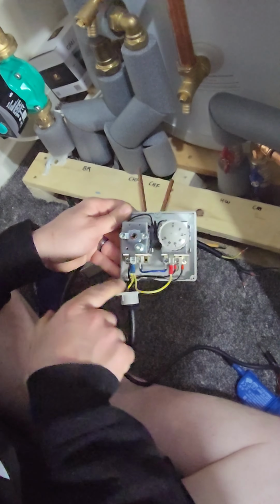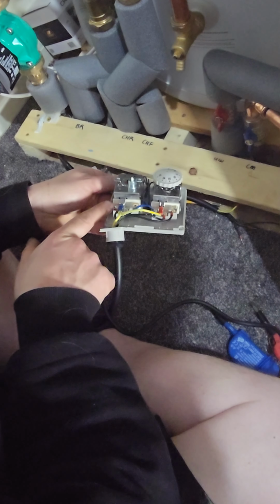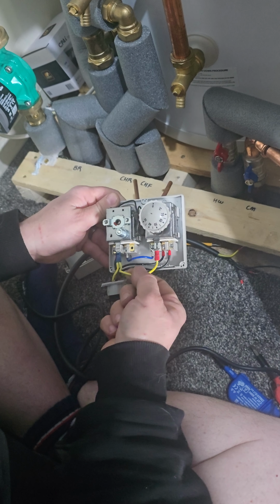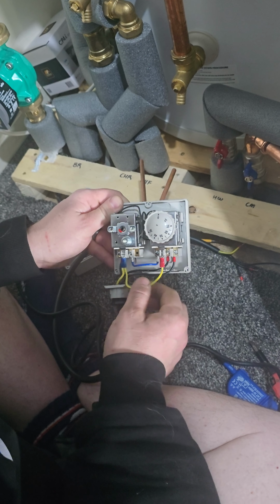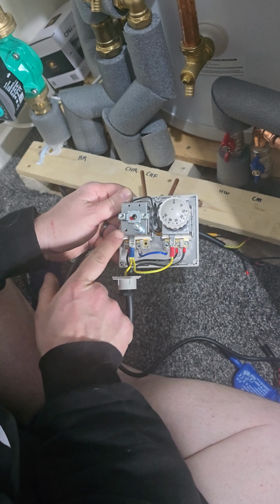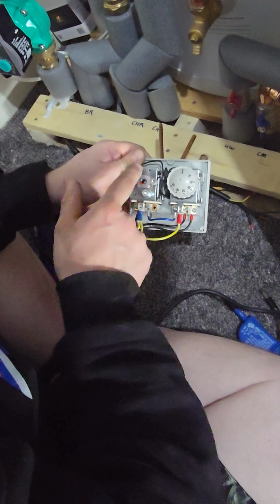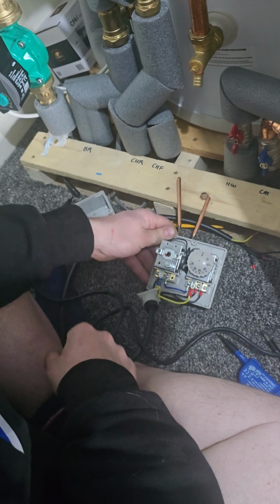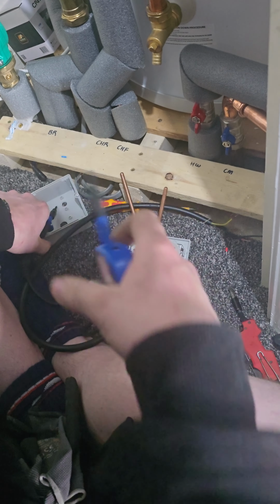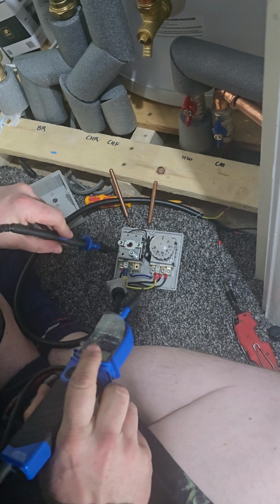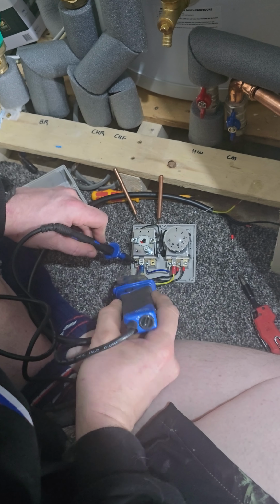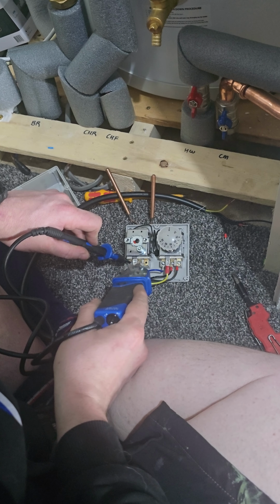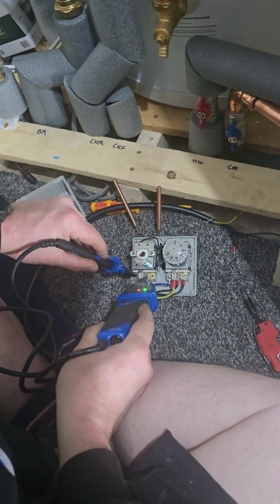This is your thermostat. So how it works is you get your common coming into here, which actually says common on this one. Obviously earth is earth, but this blue one isn't neutral. This is where it gets complicated. So this common comes in here, and if there is power, because it's not overheated, let me get my tester and I'll show you. So we've got common coming in from the left here, and then if this hasn't overheated, there should be power out to this blue one here, and there's continuity tested.